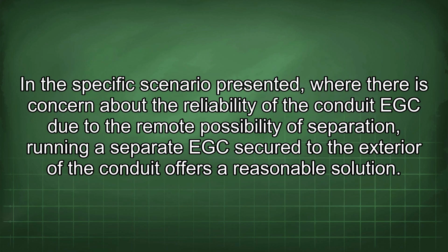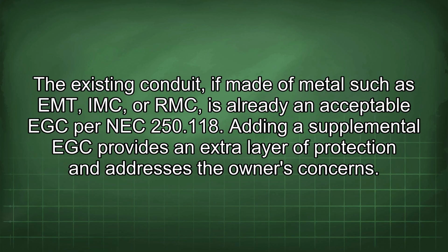In the specific scenario presented, where there is concern about the reliability of the conduit EGC due to the remote possibility of separation, running a separate EGC secured to the exterior of the conduit offers a reasonable solution. The existing conduit, if made of metals such as EMT, IMC, or RMC, is already an acceptable EGC per NEC 250.118. Adding a supplemental EGC provides an extra layer of protection and addresses the owner's concerns.